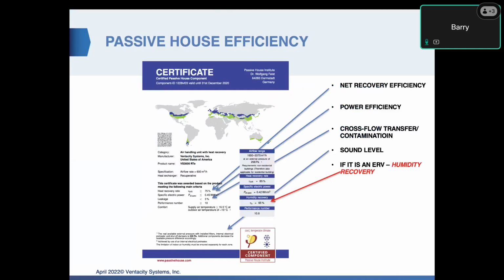Passive House certified is something we are proud of, and we were the first commercial ERVs Passive House certified. There are a lot of commercial HRVs, larger capacity units, that were certified, but we were the first ERVs. This is a very high bar to get over, so it's very high net recovery efficiency of how much energy you're recovering, but it's also fan efficiency, how much power you're using. We're going to talk about COP, coefficient of performance. That plays a big part of that. It's also important not to have cross-flow contamination, and the sound level. When you build really efficient buildings and you have tight, well-insulated envelopes, sound levels become a factor, so that's important as well.